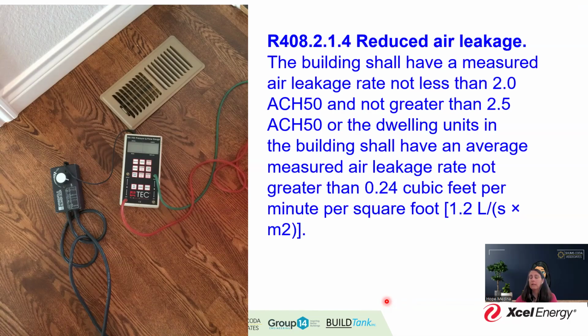2.5 if you're in 1 through 3. Or 0 through 2, sorry. You're doing this at 50 pascals. Now, we all understand that we do have another testing metric option when it comes to air change or the air leakage testing, which is the cubic feet per minute. Now, this is where you're going to find the value for that one.